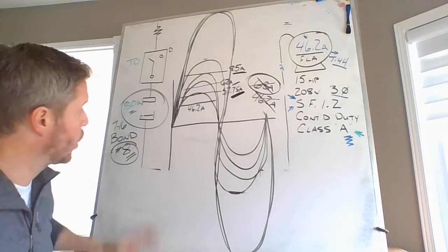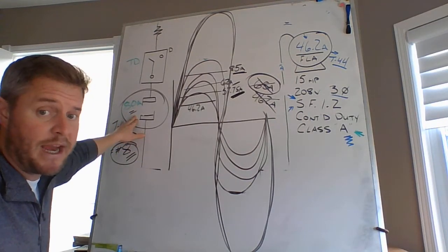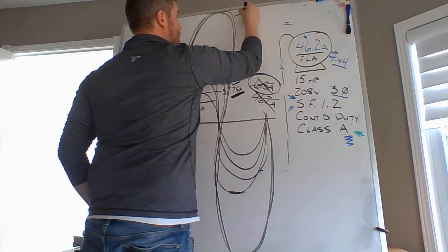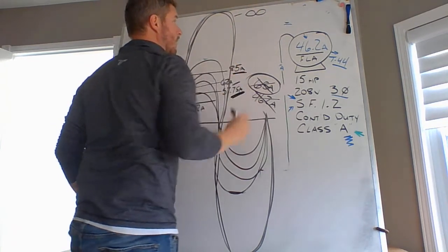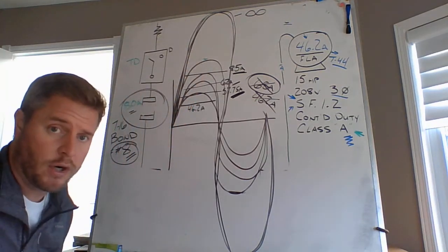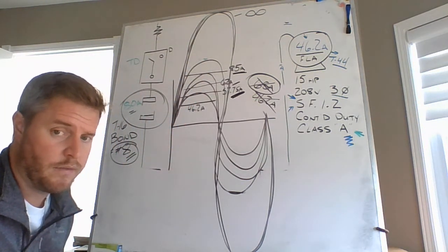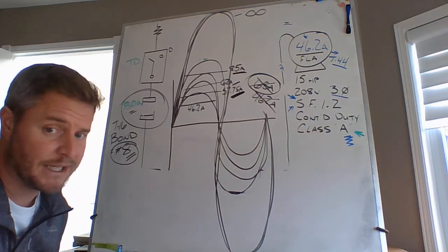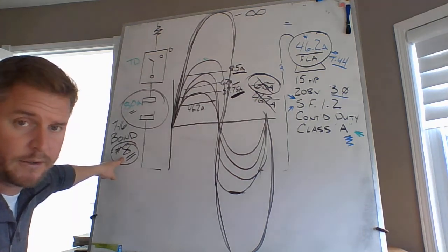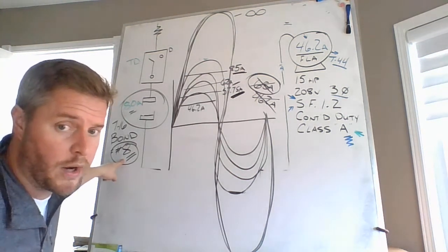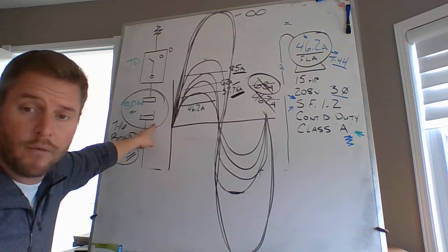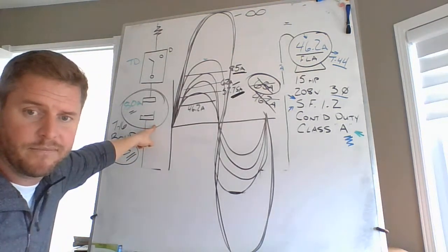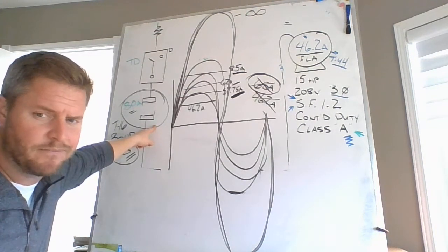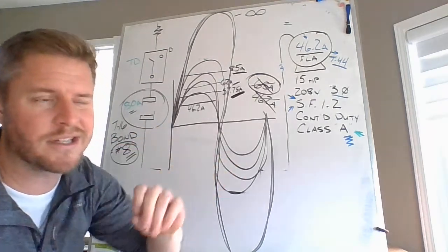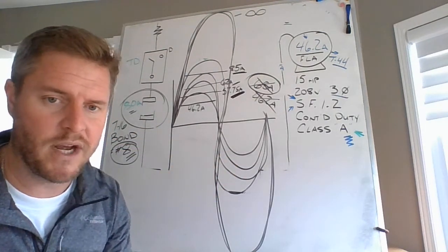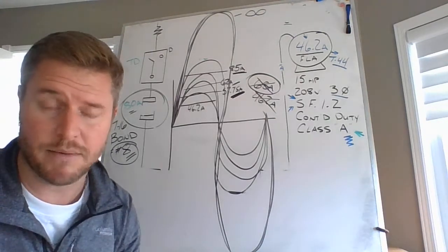And if all of a sudden that overcurrent device sees more than its maximum of 80 amps coming up here to an exponential, this is the infinity symbol right here, an infinite amount of current coming through, that overcurrent device is going to be facilitated rapidly via this number 8 bonding conductor. When we have a fault, we want all of the current to flow so that it opens my overcurrent device as fast as possible. This is why you install fuses and circuit breakers. Not to limit current. It's not to be like, oh, you're drawing 16 amps, that's too much, I'm going to shut off a 15 amp breaker. No, it's because you're drawing 4,000 amps on a short.